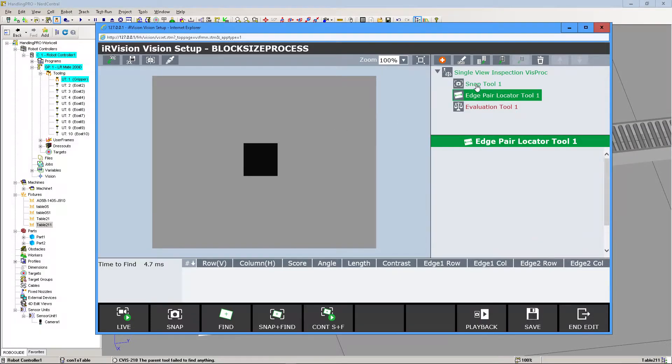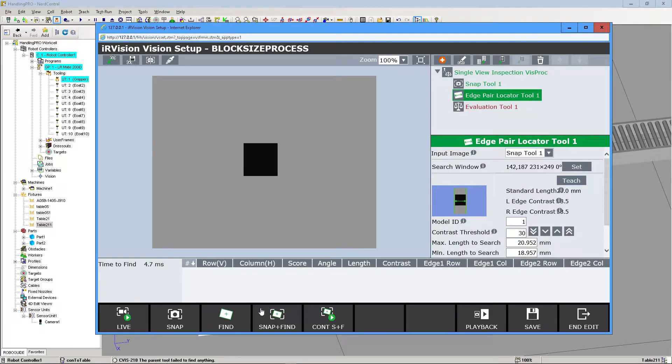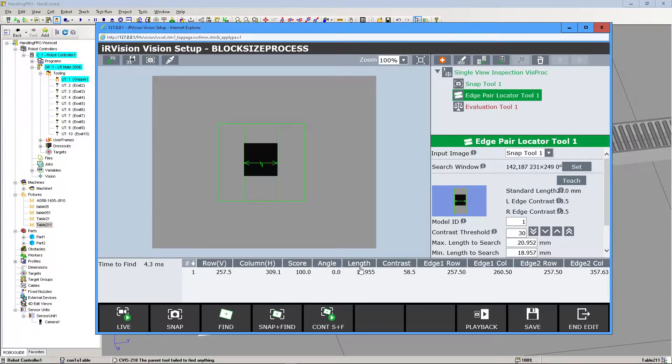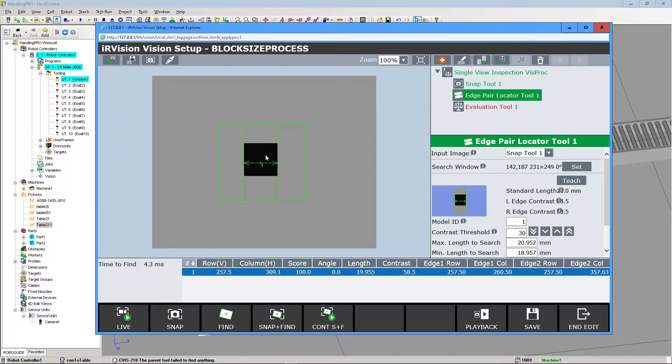Now that our camera is calibrated properly, to check this we're going to click on Edge Pair Locator Tool and do Snap and Find. We can see here that the length is 19.955, and we define the block in our work cell to be 20 millimeters. So that's how we know we're good to go.